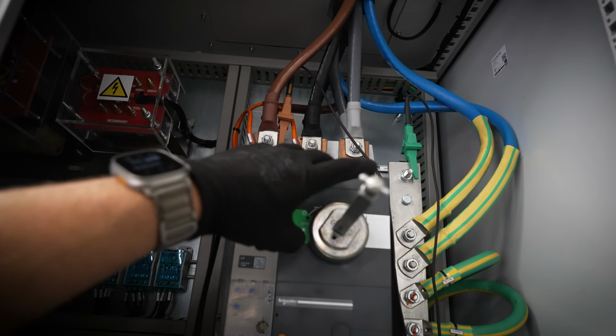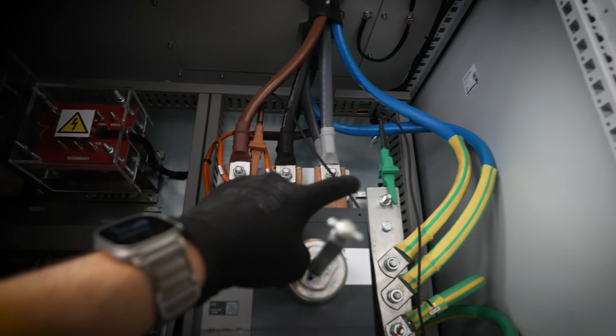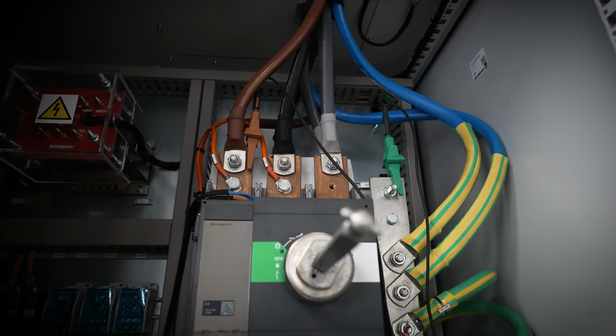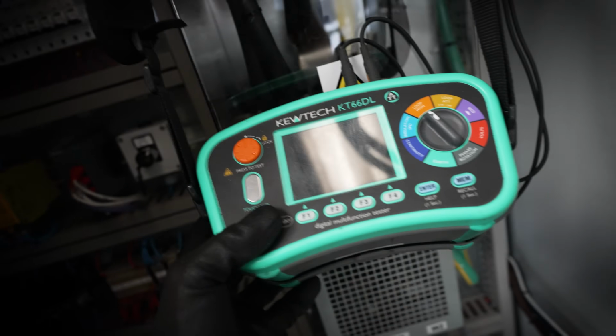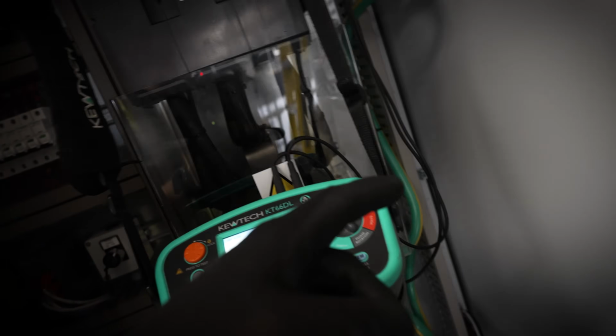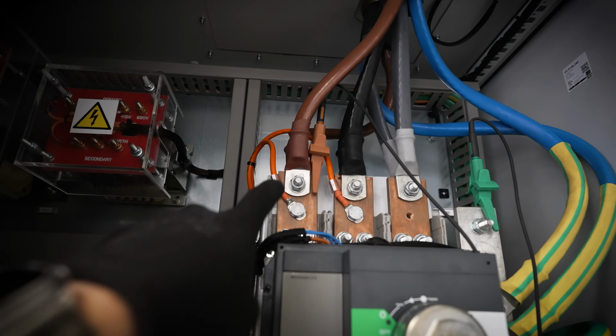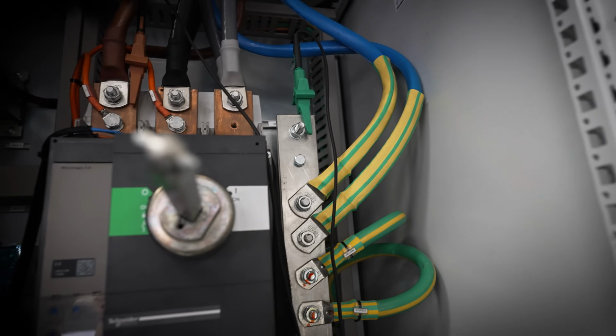And one on Earth. So this is ready to do R1 and R2 between phase one and Earth. I'm going to go through all three phases just to make sure that that's sweet. We can get this on. That's not going to be much good without going to the other end where we put this away in the panel and creating a link between L1 and Earth.